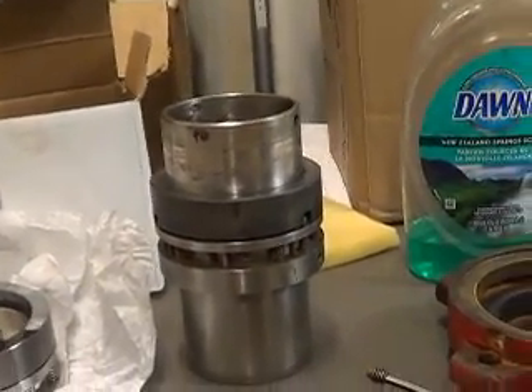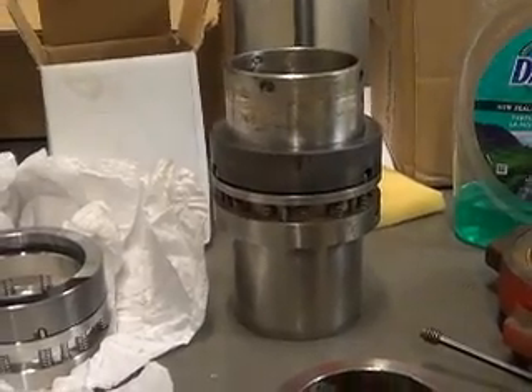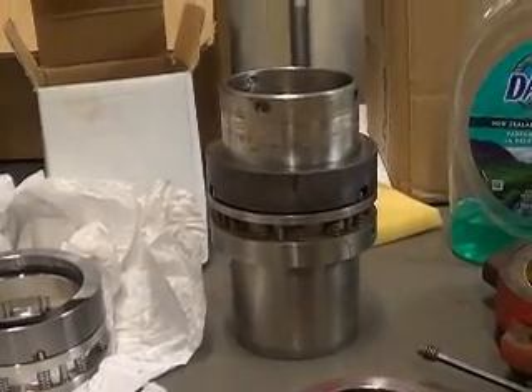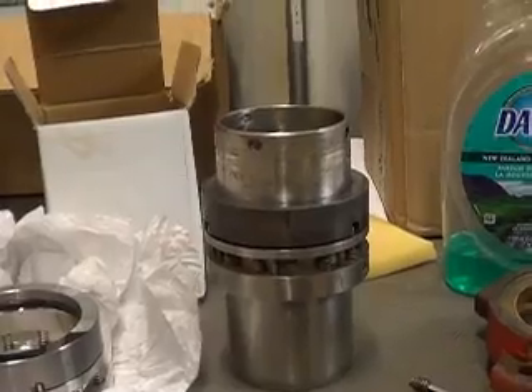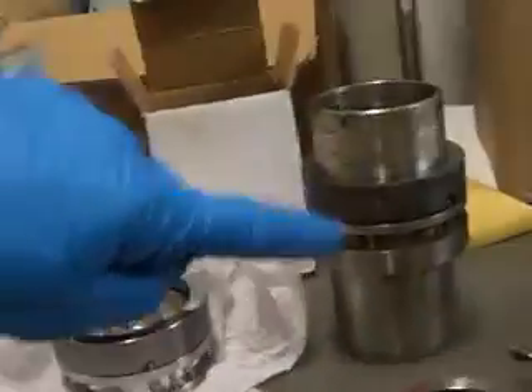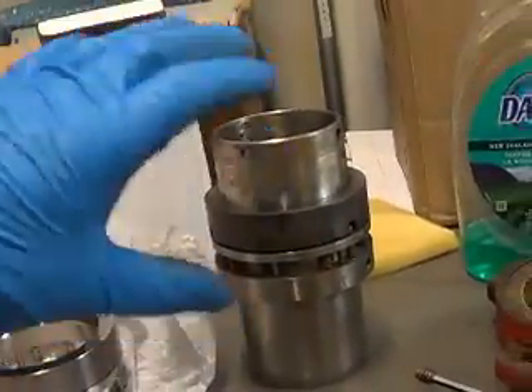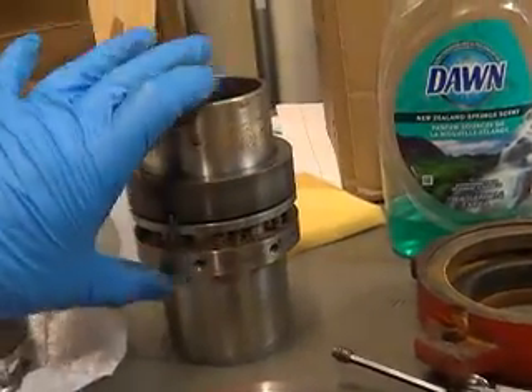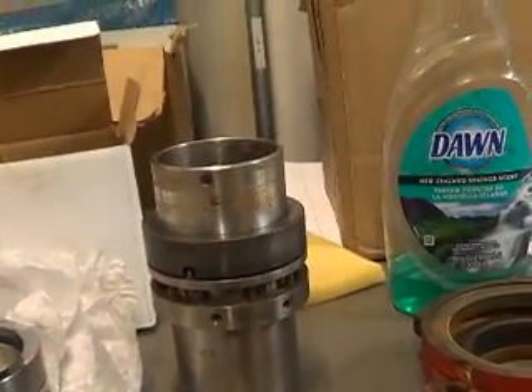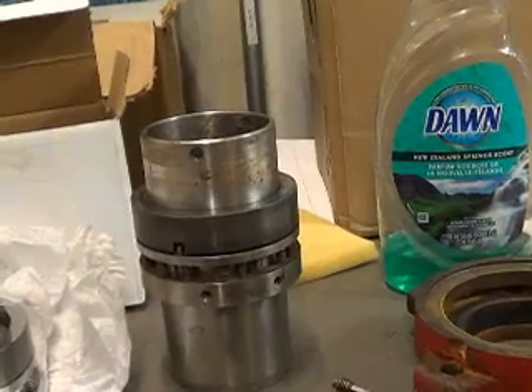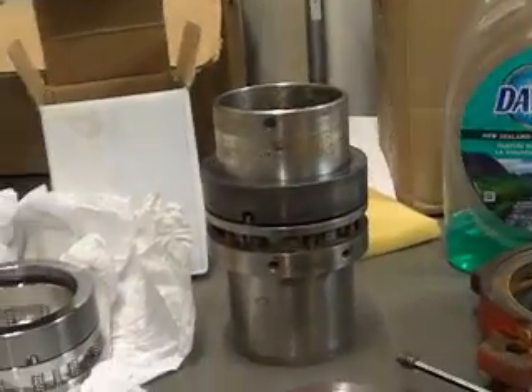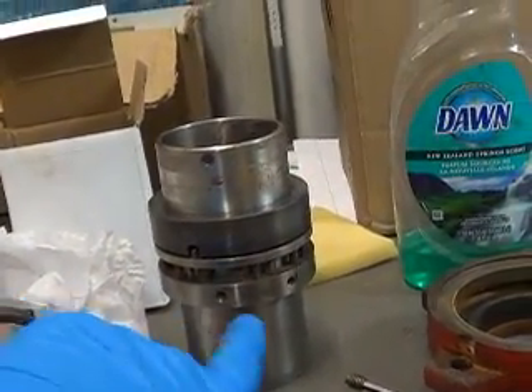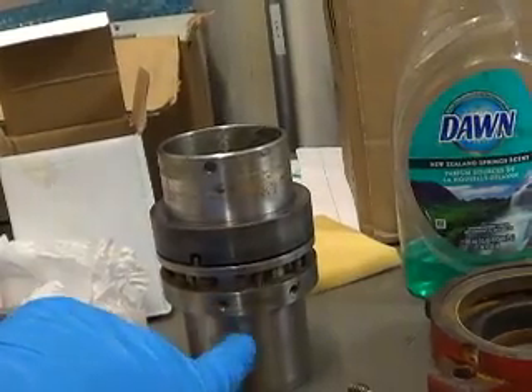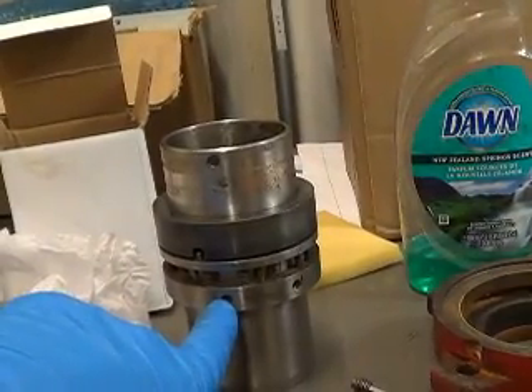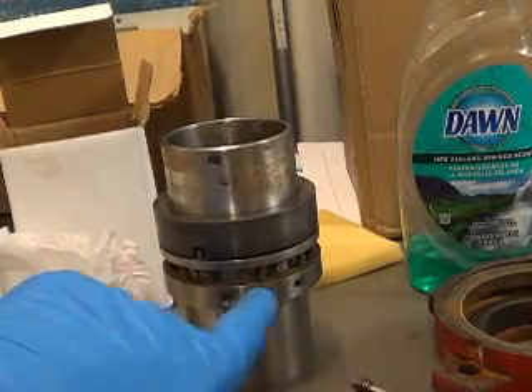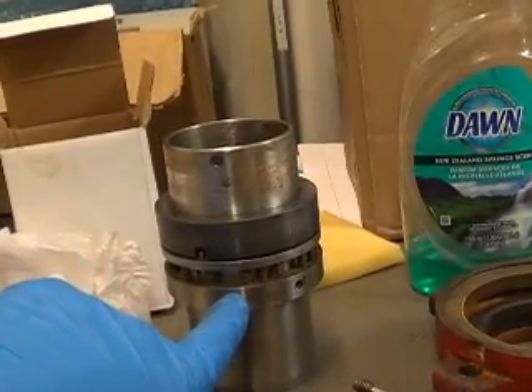I'll turn you back on when I get you set up, and you can watch me put the pieces together on the pump. For now, I'm going to swap over these two pieces and install it. It doesn't give a specification for spring tension that I can find, and I've talked to several seal people, so I'm going to use the old holes. There's a mark on this sleeve from the set screws, and that's what I'll use to set the depth of this part of the seal.